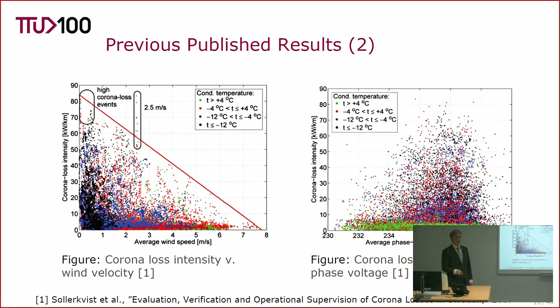In the thesis, I propose to use PMU measurements in order to calculate transmission losses as components. The main hypothesis is that PMUs enable the transmission line to be monitored in more detail so that these components of losses can be calculated directly. In order to do that, I have derived the necessary equations and analyzed uncertainty propagation in the monitoring application. I have tested the method on real measurement data and validated the results of monitoring corona losses based on analyzing the same dependencies we saw in the previous figures and comparing these dependencies.